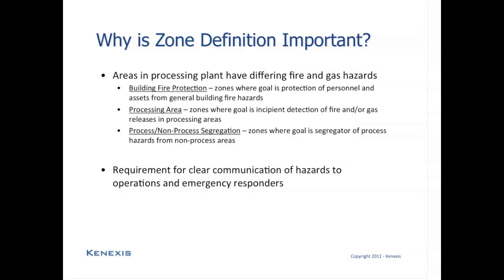Some areas may be prone to pool fires where other areas may be prone to gas releases or gas jet fires. So understanding what hazards are present through the hazard process is going to help us to define what the zones are, segregate the zones from each other, and then set the performance targets internal to those zones. Also, there is a special type of zone where you're trying to segregate a process area from a non-process area. This would include things like air intakes into control rooms, motor control centers, and also airlock doorways that separate a process area from a control room.